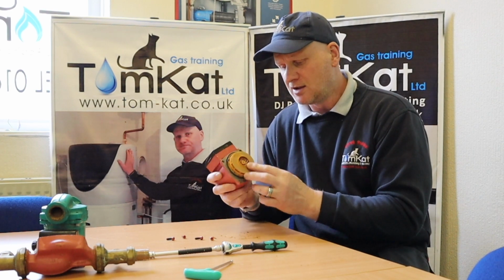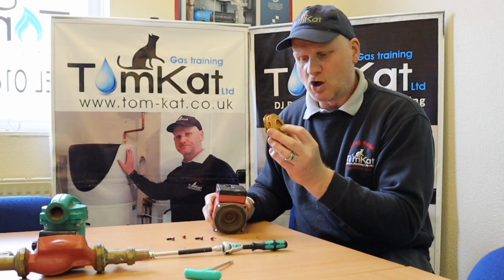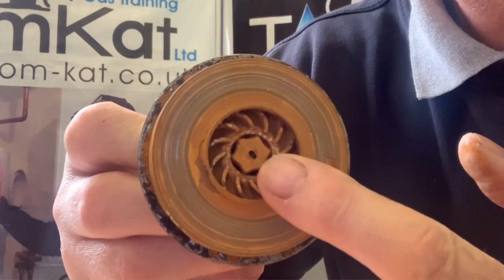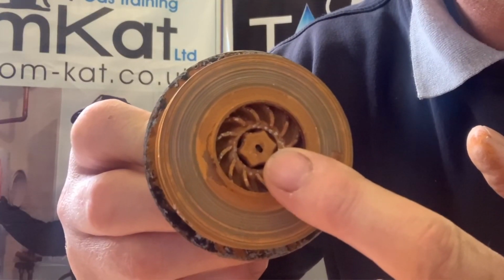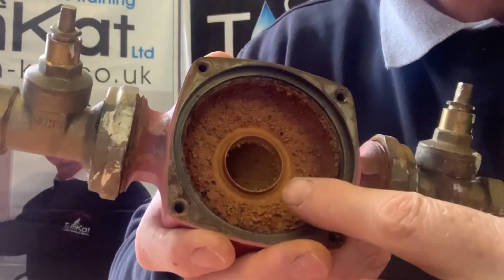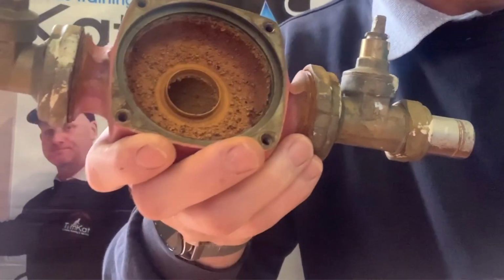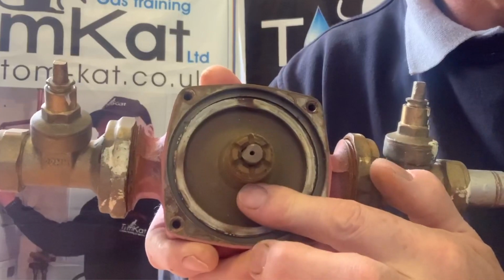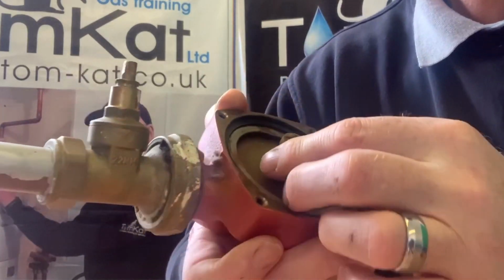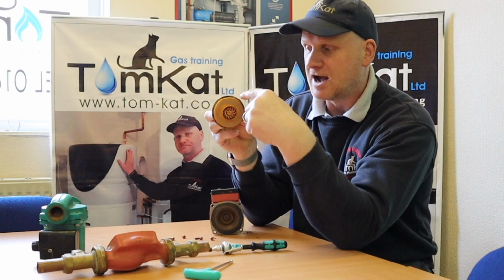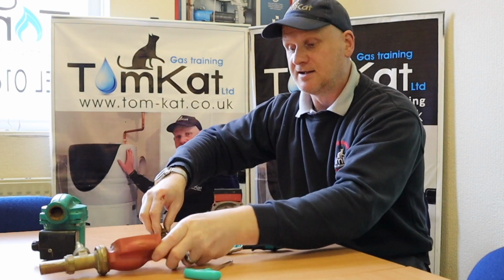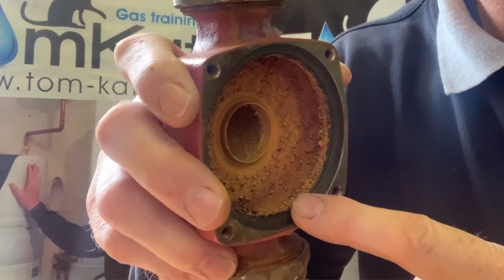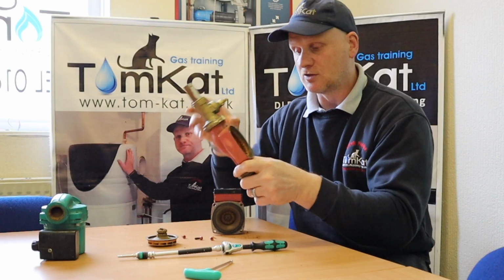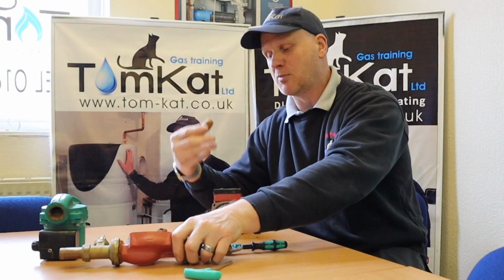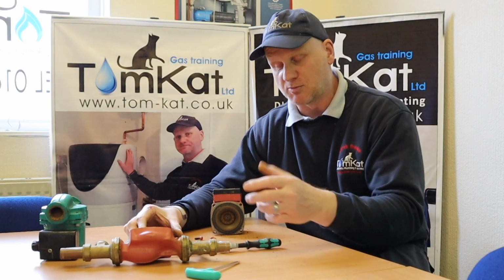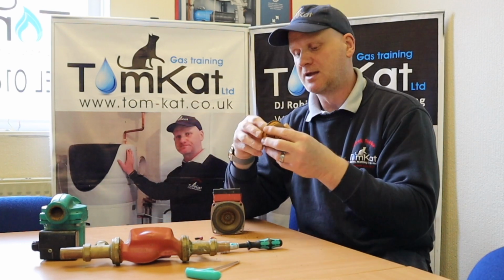Now the impeller, what happens is the water, which you can't see in here very well, comes through here. So the water comes up that hole there, and the impeller sits on the top. The water has to go through the middle of there, and then the water's flung out, and then it goes down through a slot. Okay, so that's how the water gets into the pump and out of the pump, and all central heating pumps are pretty much working on the same principle.